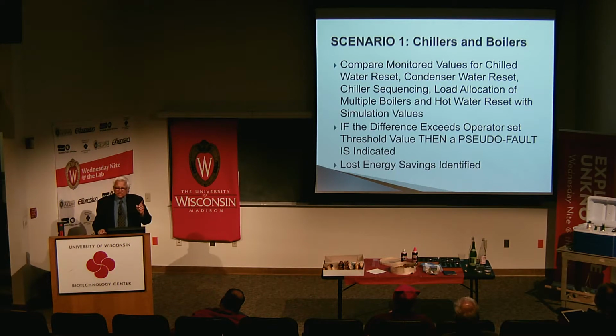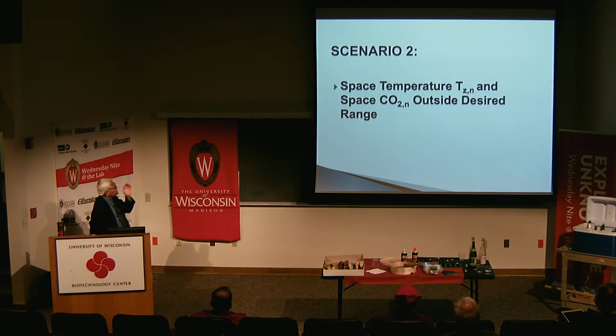So as you can see, fault detection is very important. You save energy, and you also prevent environmental conditions from being violated. You also ensure thermal comfort is maintained. Now let us take another interesting scenario. In this case, say CO2 is okay in the zones, but temperature is not okay. How do you diagnose where the fault is?